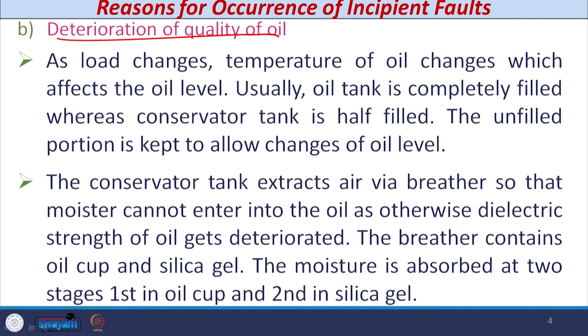The second reason is deterioration of oil quality. The transformer has two tanks: the main tank, which is completely filled, and the conservator tank, which is half filled to allow changes in oil level due to load variation. The conservator tank extracts air via a breather so that moisture cannot enter the oil, since moisture deteriorates the dielectric strength of the oil. The breather contains an oil cup and silica gel. Moisture is absorbed in two stages: first at the oil cup and second in the silica gel.